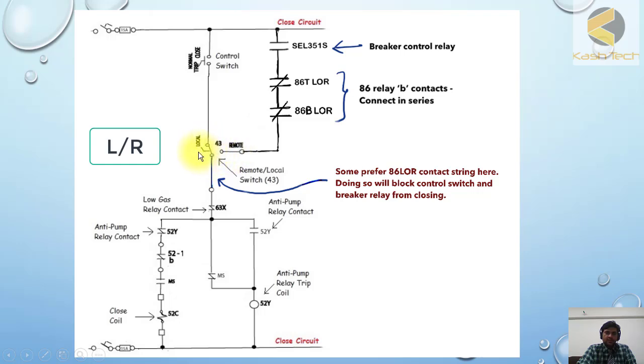This is the local remote operation. If the selector is at local, then the pulse will be forwarded. If it's at remote between SCADA, then it will be forwarded to SCADA. This is a breaker control relay that will initiate the pulse.